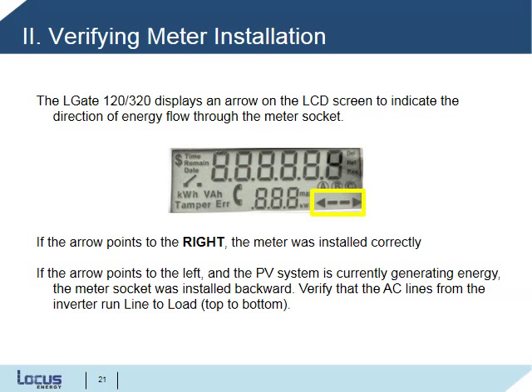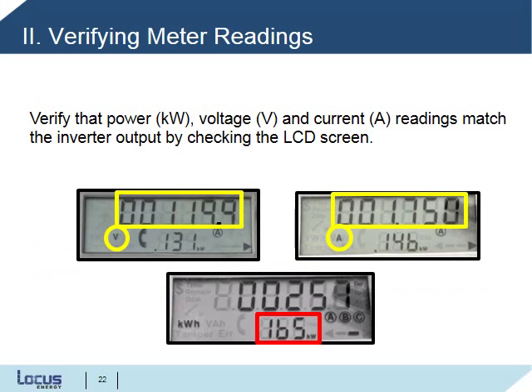To verify meter installation after startup, check the arrow on the LCD screen, which is shown here in the lower right corner. This arrow indicates the direction of energy flowing through the meter socket. If the arrow points to the right, the meter was installed correctly and we're getting positive power readings. If the arrow is pointing to the left and the PV system is currently generating energy, this means that the meter socket was installed backwards. You should verify that the AC lines from the inverter run line to load or top to bottom. Next, verify that the power, voltage, and current readings match the inverter output by checking what's displayed on the LCD screen.